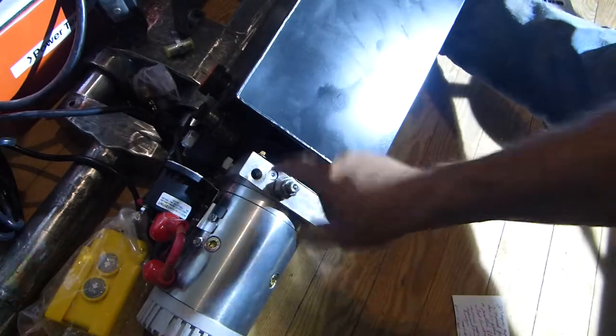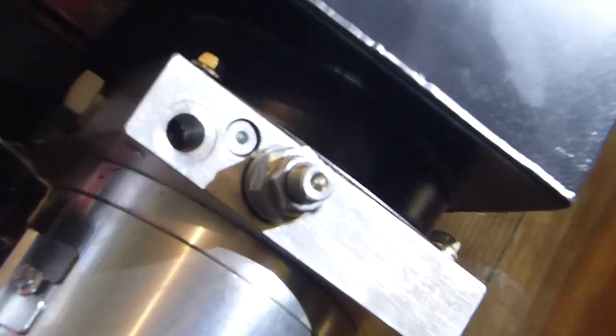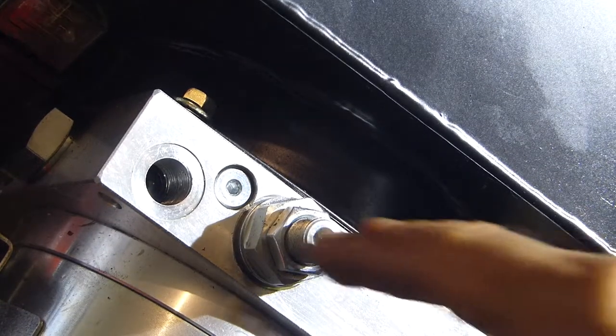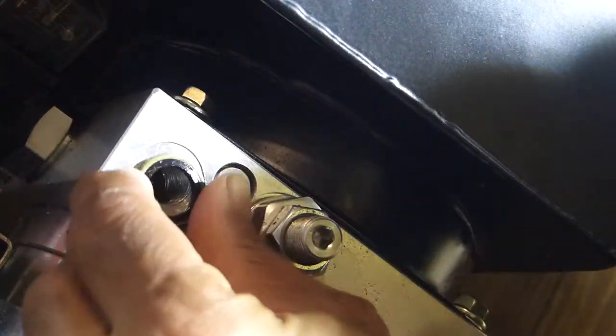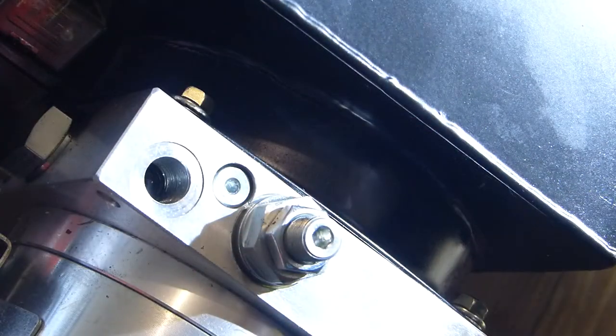This port is not beveled on this device. It is recessed to some degree, so you're going to use a gasket. Sorry about that, see if I get that in focus a little bit. You're going to use a gasket when you change this out to any upgrade or change out. Through compression it's going to make the seal. This is about a 3000 psi pump.